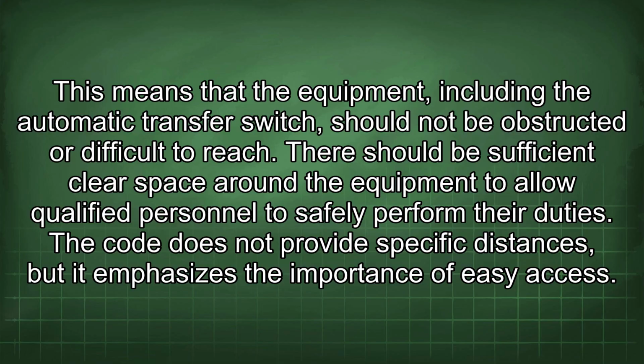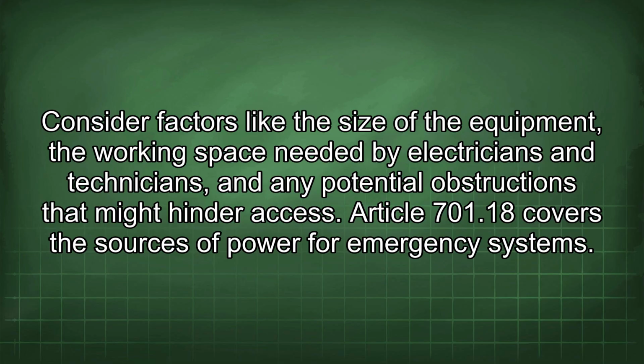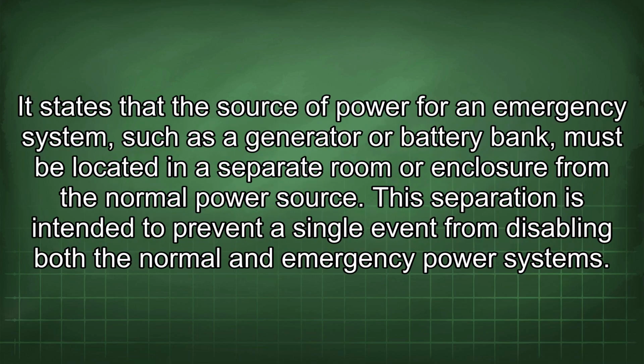The code does not provide specific distances, but it emphasizes the importance of easy access. Consider factors like the size of the equipment, the working space needed by electricians and technicians, and any potential obstructions that might hinder access. Article 701.18 covers the sources of power for emergency systems. It states that the source of power for an emergency system, such as a generator or battery bank, must be located in a separate room or enclosure from the normal power source.